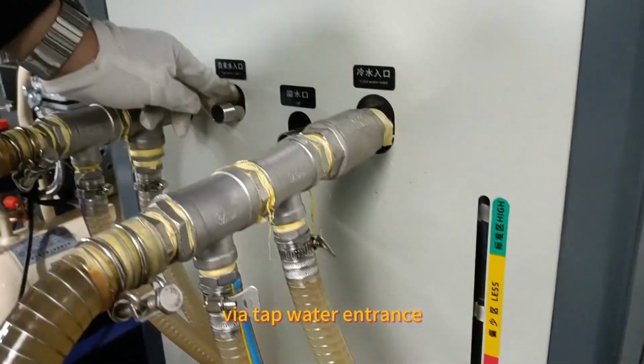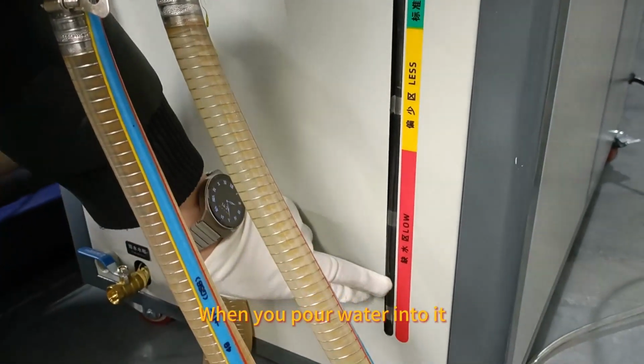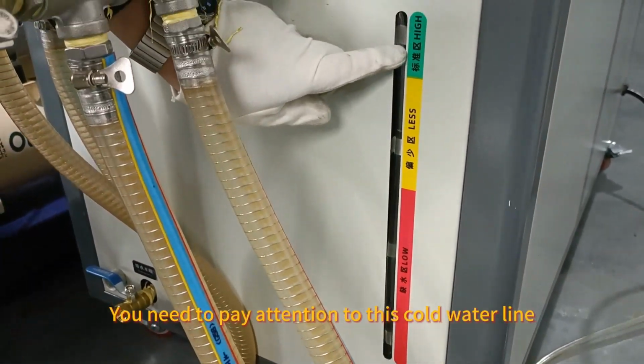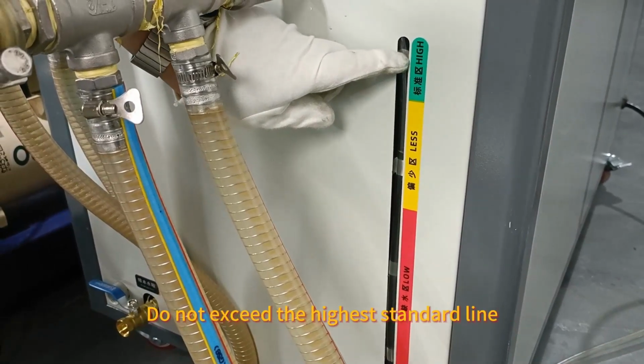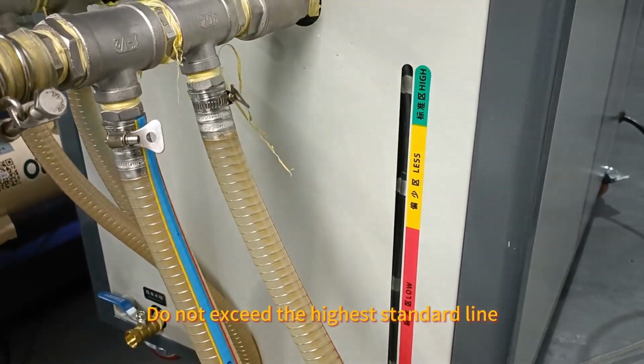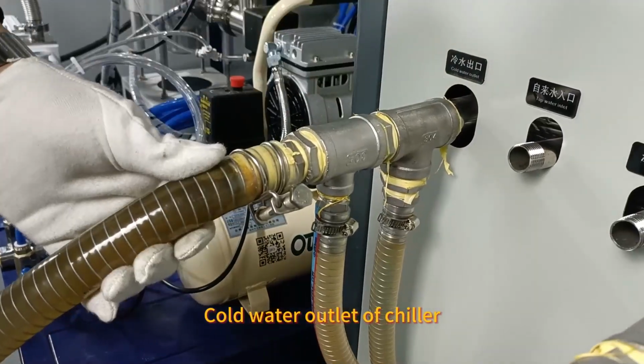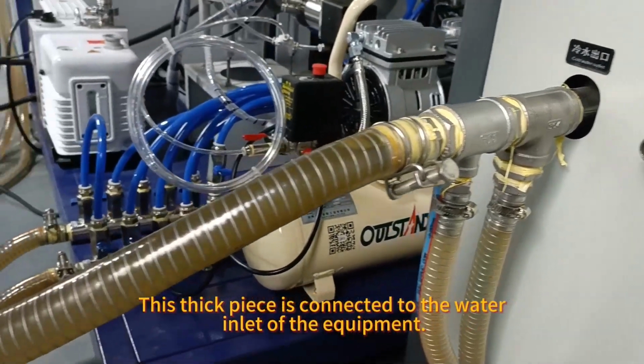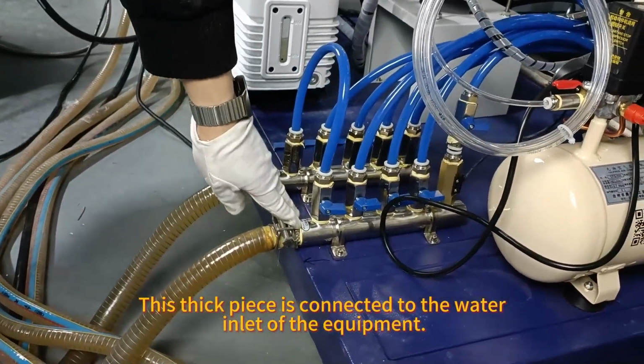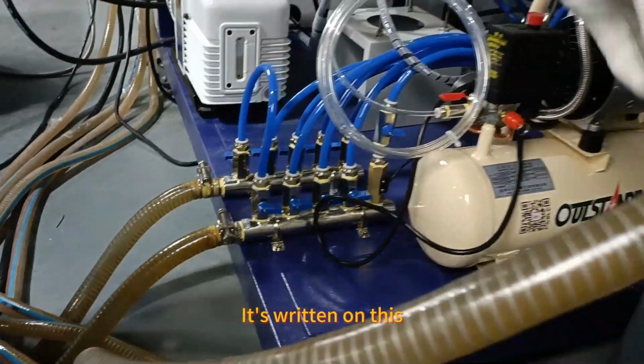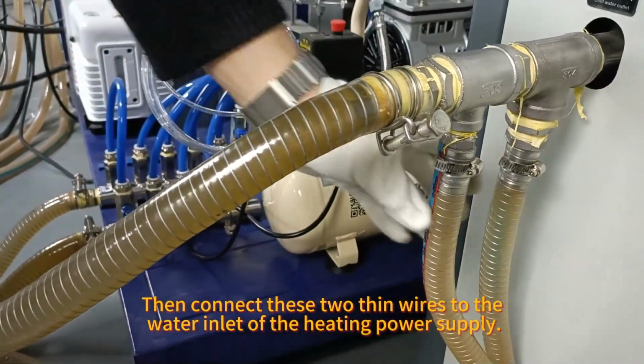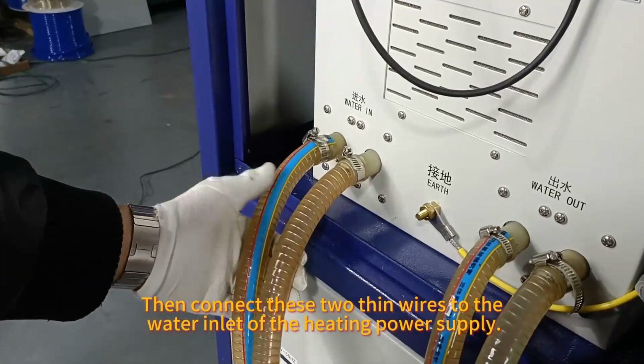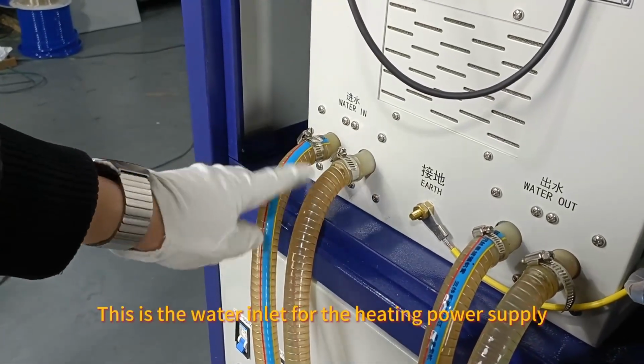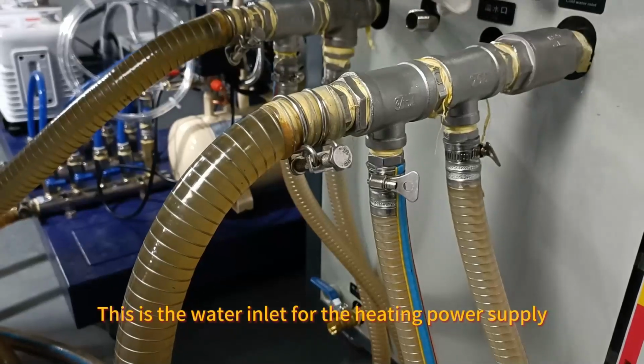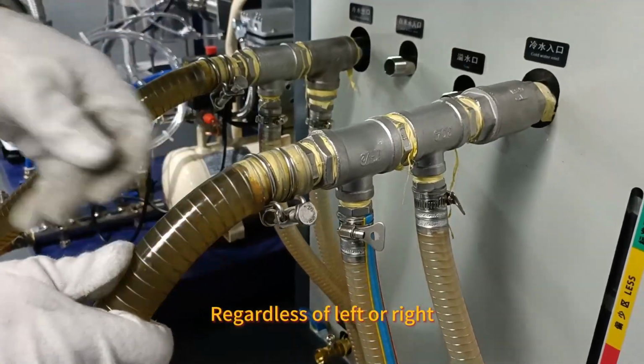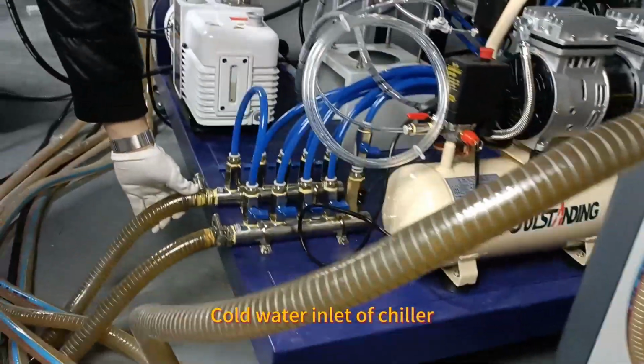When you pour water into the tap water entrance, you need to pay attention to this cold water line. Do not exceed the highest standard line. Cold water outlet of the chiller: this thick piece is connected to the water inlet of the equipment. It's written on this. Then connect these 2 thin wires to the water inlet of the heating power supply. This is the water inlet for the heating power supply. Regardless of left or right, it connects to the cold water inlet of the chiller.